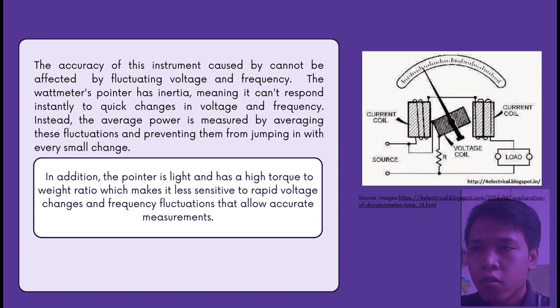The accuracy of this instrument is due to it not being affected by fluctuating voltage and frequency. The wattmeter's pointer has inertia, meaning it cannot respond instantly to quick changes in voltage and frequency. Instead, the average power is measured by averaging these fluctuations, preventing the pointer from jumping with every small change. In addition, the pointer is light and has a high torque to weight ratio, which makes it less sensitive to rapid voltage changes and frequency fluctuations, allowing accurate measurements.